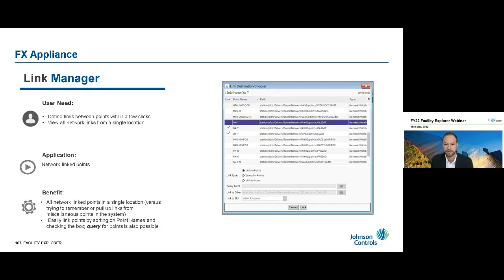Similar to the Schedule Manager, the Link Manager is a simple tool to manage our links, which is the global data shared between multiple controllers or even supervisors. For example, we might have an outside air temperature point that we want to share with all our air handling units. We can quickly go into the Link Manager, search for the point we want, for example OAT or outside air temperature, then create a link to the controller that will need to use this point.